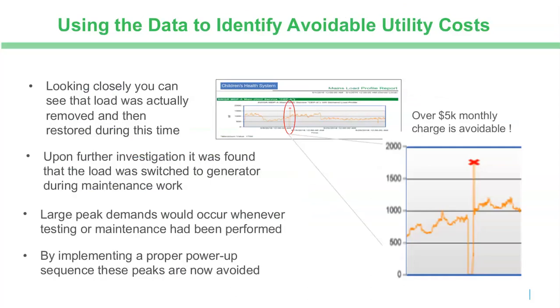When we looked closer, we saw that there was a loss of power and then a restoration of power at 3:15 a.m. So we started looking at what was going on at 3:15 a.m. and why that would have occurred. What we found is it was part of their maintenance and testing, and the restart procedure for their facility was not working right, so all of the loads were turning on at the same time. That's a simple fix: by better sequencing the loads, they would be able to avoid that expense.